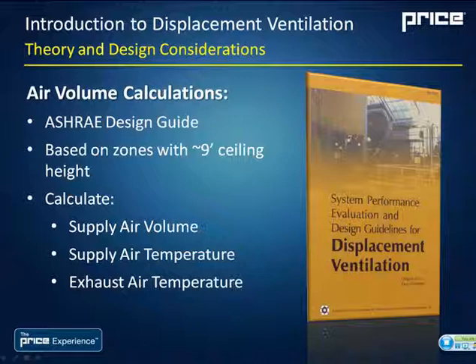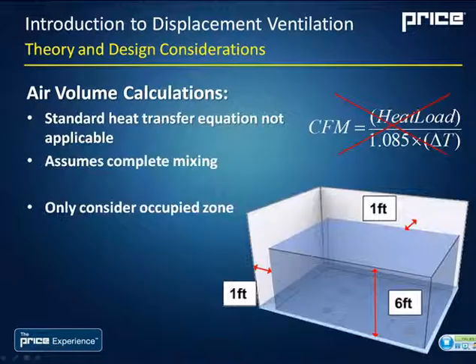Now the air volume calculations are done a little bit differently with displacement ventilation, simply because we're considering the occupied zone only. We follow the ASHRAE design guide for displacement ventilation, and we've summarized that in our green catalog as well. This was based on a research study based on a variety of different rooms, different load densities, different types of rooms. The majority of them had around a 9-foot ceiling height, and what these air volume calculations are going to do is help you calculate your supply volume, your supply temperature, and the exhaust air temperature as well.